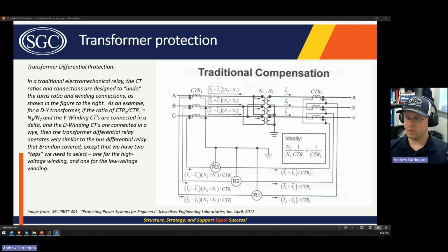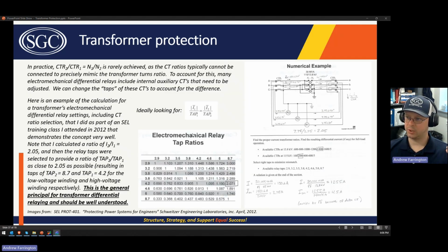The relay itself, it's not often that you can actually connect the CTs to ideally match the inverse turns ratio of the transformer. So the electromechanical differential relay has various taps for both the high side and the low side that you can use to account for any differences between the ideal ratio for the CTs as compared to the ratio of the transformer. So we'll get into I think a good example of that here.